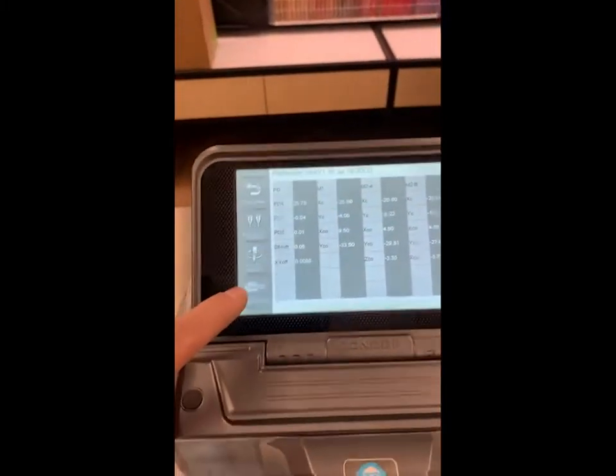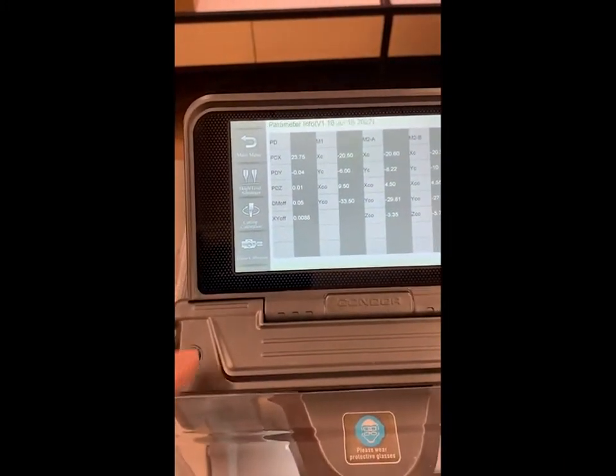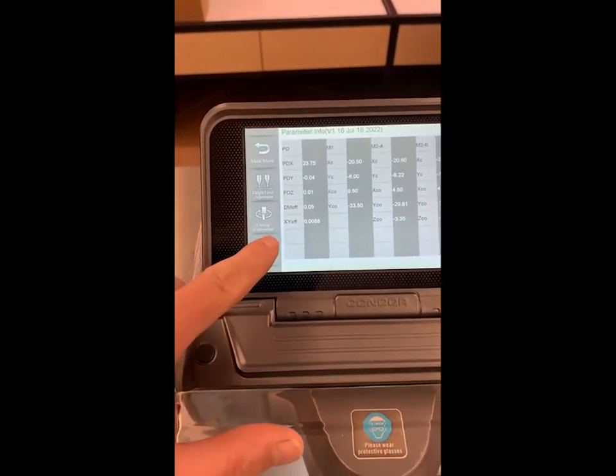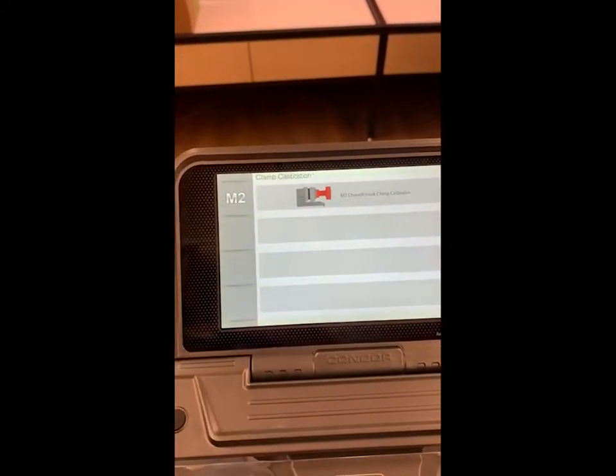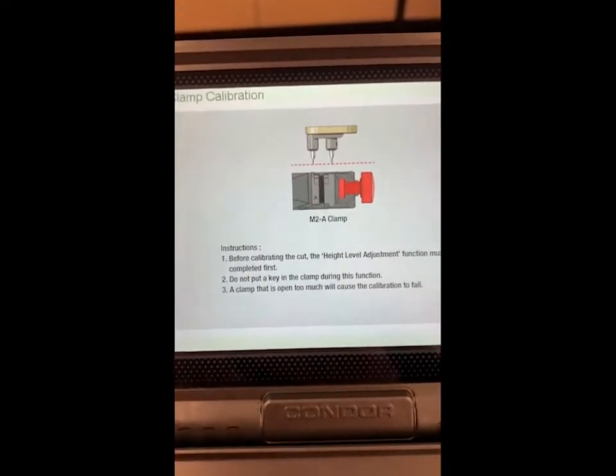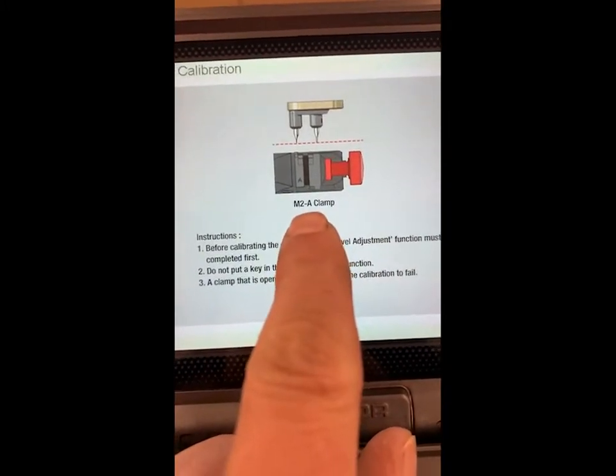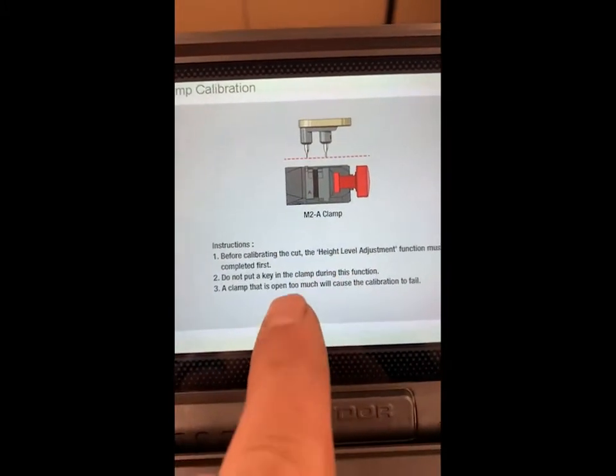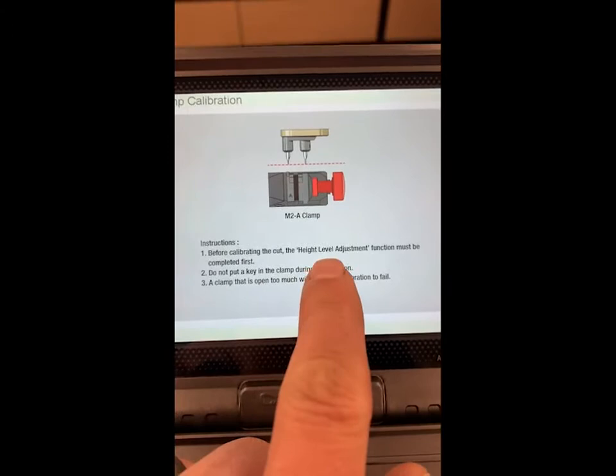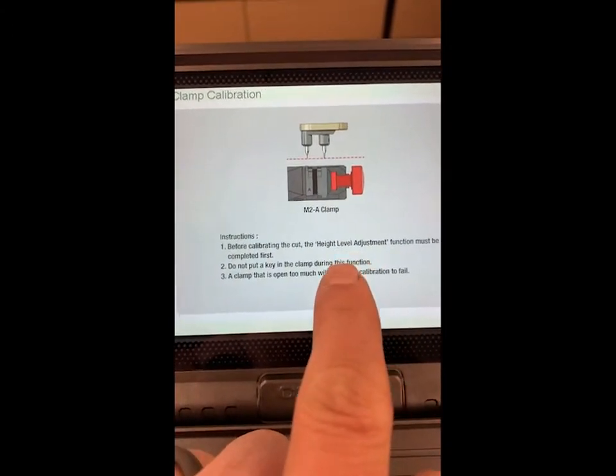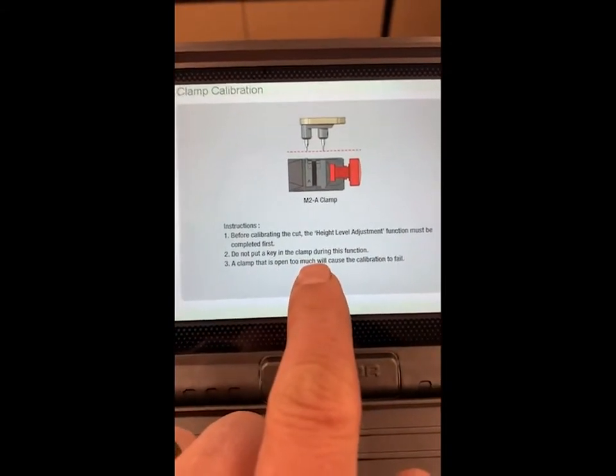Confirm. Now this step here is the one that I believe has been missing for some people that have been doing the update. So we want to do clamp calibration. When we do this, you have to touch M2, and now be very mindful of this. It says M2 clamp A. Before calibrating, you have to do height level adjustment, which is the first test. Do not put a key in the clamp, and make sure it's not open too much. So this comes out.